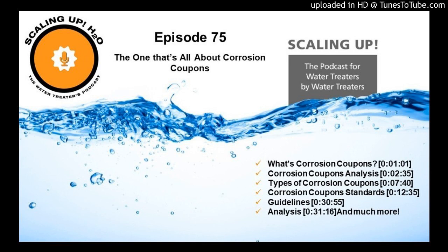The great thing about corrosion coupons is they're checked at a shorter interval than equipment inspections, so you can make slight adjustments to your program and see if you're increasing or decreasing the effectiveness of the system.